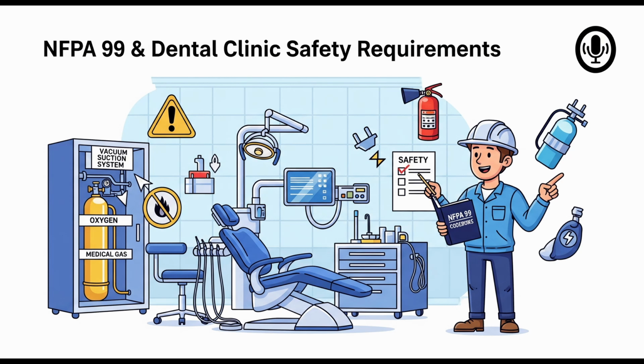And one more piece on operations. The Responsible Facility Authority, or RFA, Section 5.1.11.1 requires each facility to designate one, and 15.4.9 applies this to Category 3 facilities like dental. This person is the linchpin for ongoing compliance. They're responsible for overseeing the system requirements, managing the testing schedule, keeping maintenance records. They ensure safety isn't just a one-off at installation. So someone has to own this ongoing process.